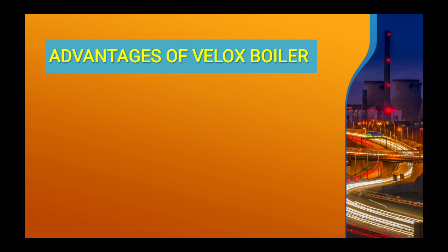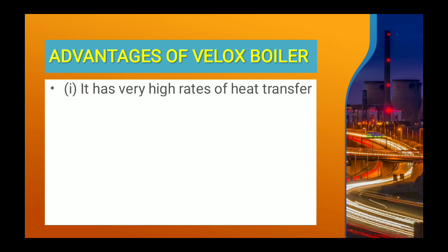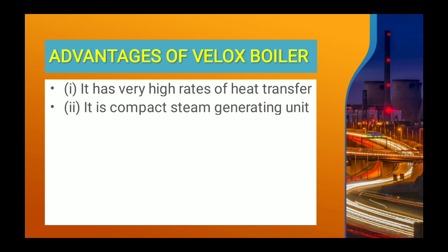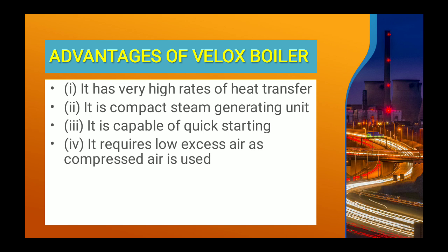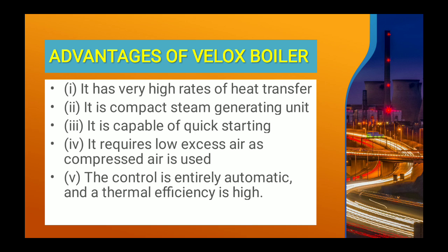And now the advantages of the Velox boiler. It has high rates of heat transfer. It is a compact steam generating unit. It is capable of quick starting with the help of the compressor. It requires low excess air as compressed air is used. The control is entirely automatic and thermal efficiency is very high. That is the main advantage of the Velox boiler.